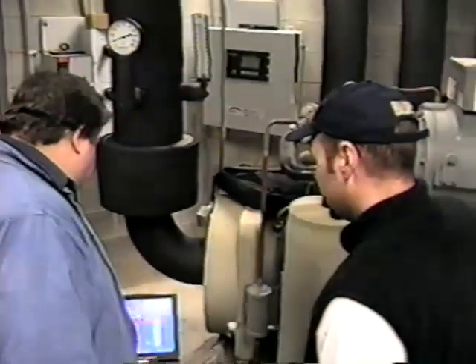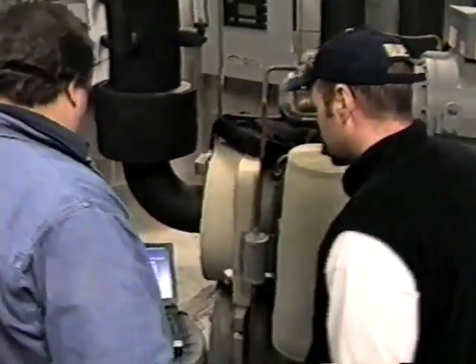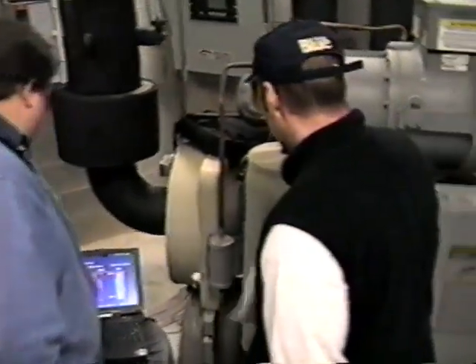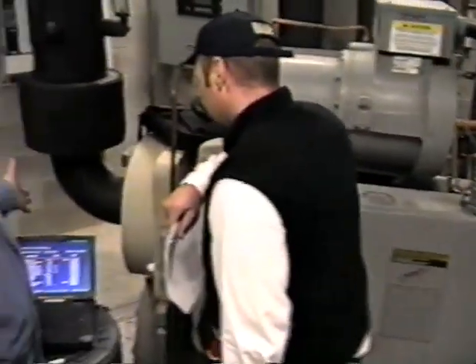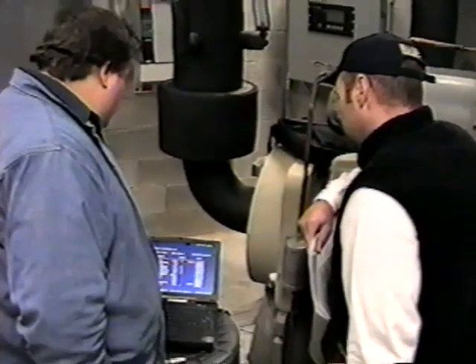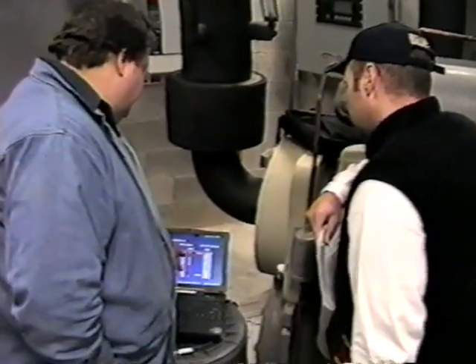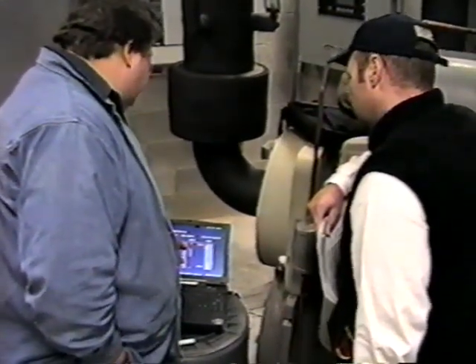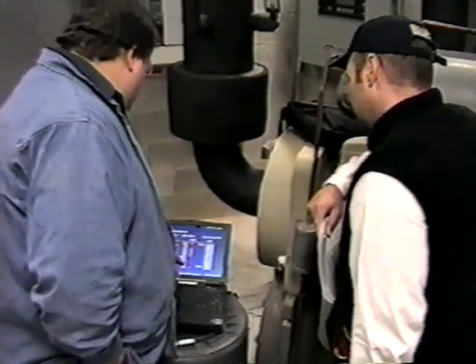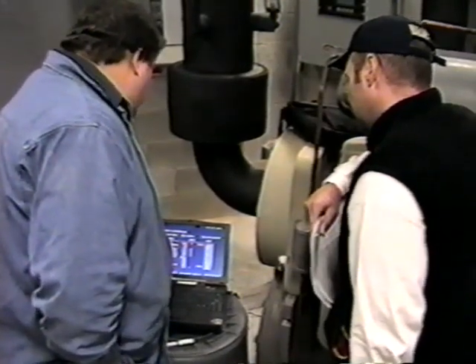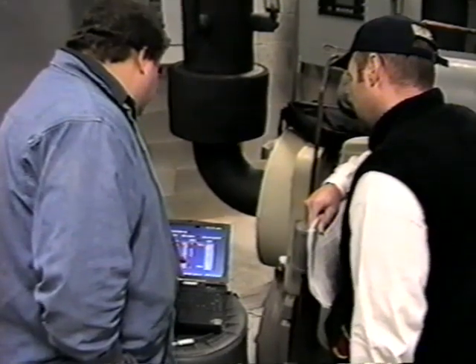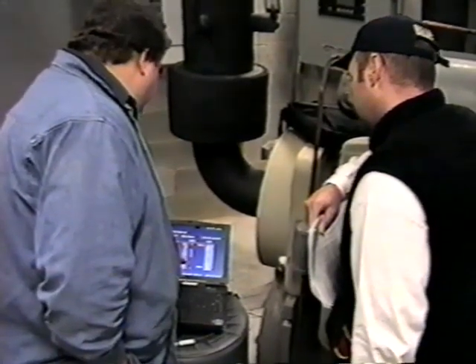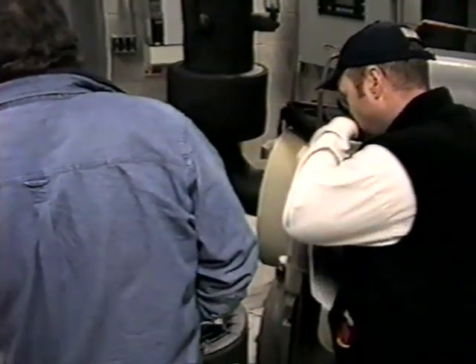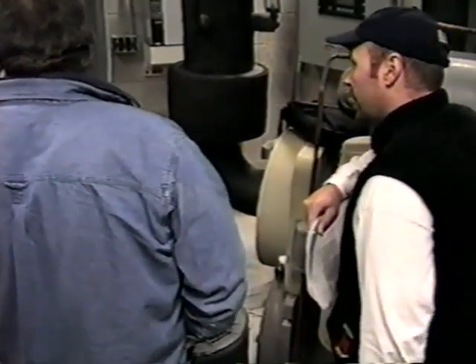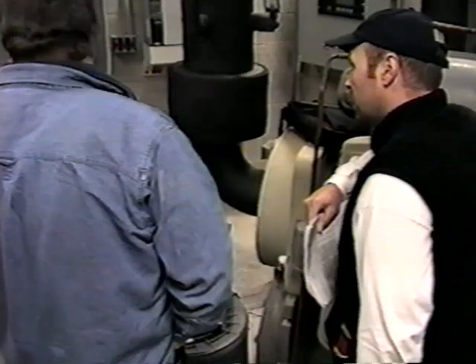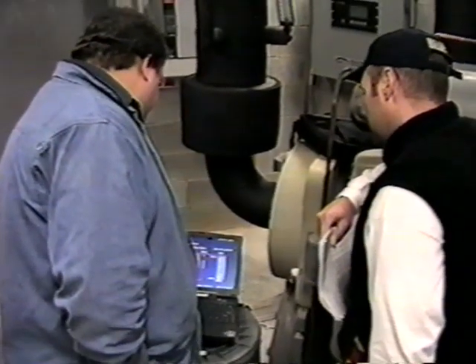So like I say, as you call for cooling, whatever your ice temperature set point is, let's say it was 21, as I climb above that with this actual ice temperature here, you're going to see this thing kick to high speed. You're going to see down here that this should kick to high speed. Right now, I don't know why it's reading high speed over there. The starter isn't pulled in, so I have to double check that.